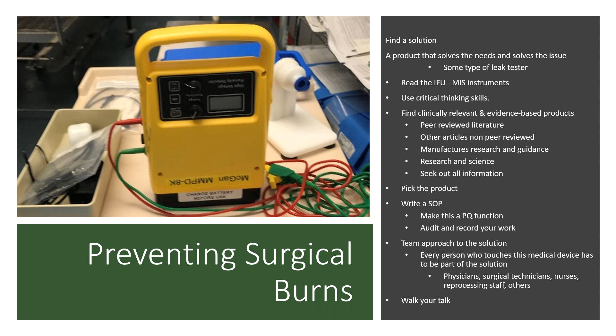So it's important that you use the high pot tester or insulation tester to adequately test the instruments if there's any nicks or item in it. So here's poll question number U3. Are you verifying insulation of your instrument using a high pot or high potential or insulation testing? And just to let you know, various insulation instruments require various voltage testing.